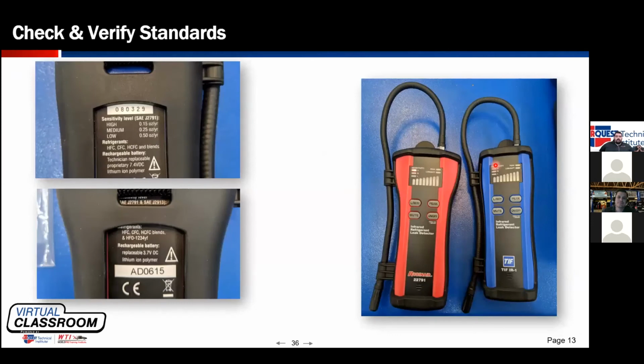These two leak detectors, one by TIF and one by Robinair, are very similar detectors. However, the red one, the Robinair one, is approved for 1234YF. The blue one is only approved for 134A. That said, if you're looking at buying a leak detector, go back and look at the MAC database and make sure that the piece of equipment that you're buying is still currently certified. I can tell you that for these two detectors, the certification has expired on both of them. Neither of them are currently in production.